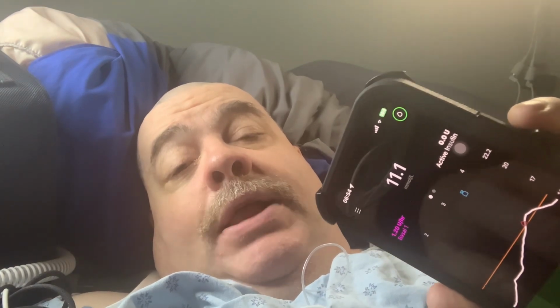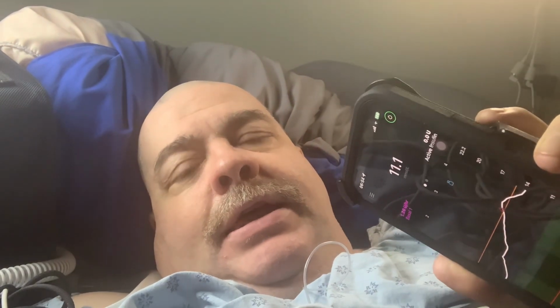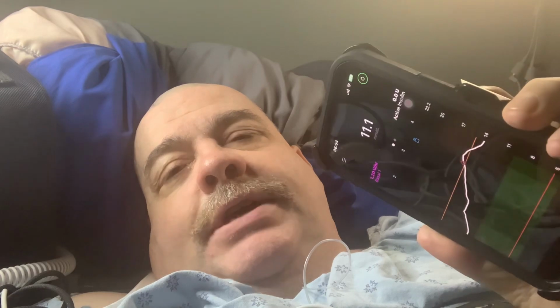One thing I would really like as a feature is that we can take the information off the old pump, feed it into this pump, so when you hook this up, the new pump will start automatically. But we don't have that, so right now I've done 24 hours on this pump, and not being in auto mode, I would definitely have to have more insulin, because coming down to 11.1, while it's not terribly high, it's still high, and going up to 15. So we'll just have to see how things go.